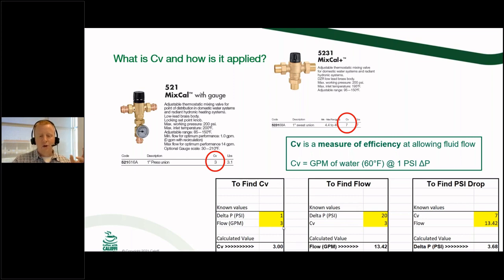This is a sheet where you can plug in just some basic numbers and find your CV, find your flow rate based on pressure drop and the CV of a valve, and find pressure drop and things like that, find flow requirements and everything here. So just to go through it again, at a 1 psi delta P with a 3 gallon per minute flow rate, you're going to have a CV of 3. That's this guy right up here, the 521 series.